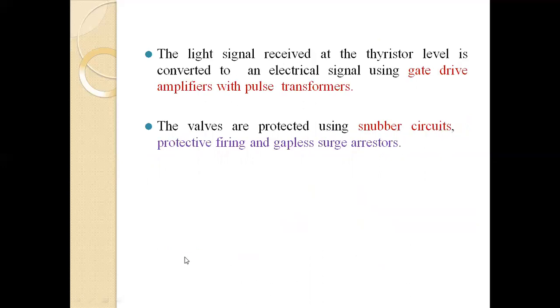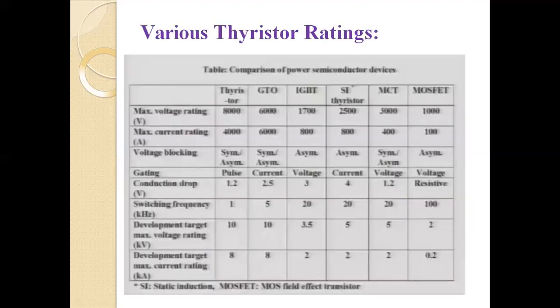The light signal received at the thyristor level is converted to an electrical signal using a gate drive amplifier with pulse transformer. The valves are protected using snubber circuit, protective firing, and gapless surge arrester.